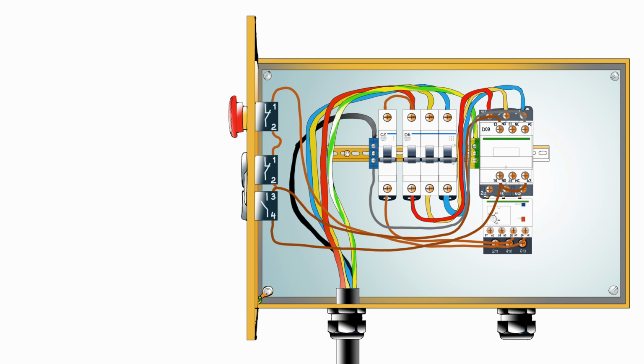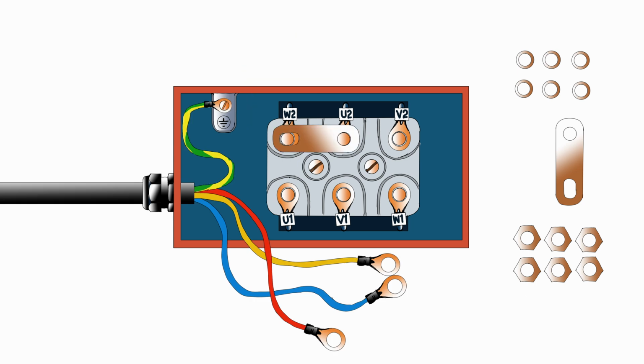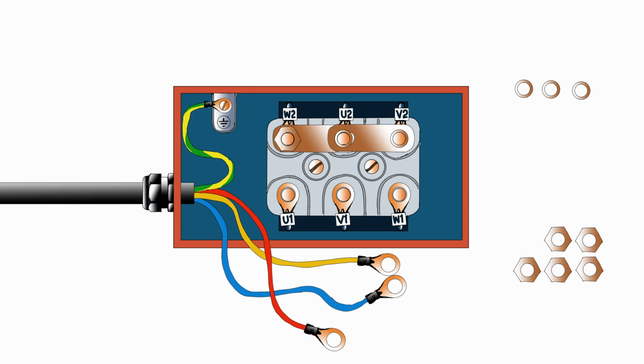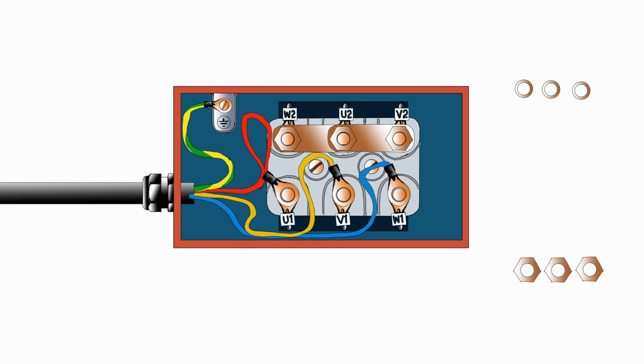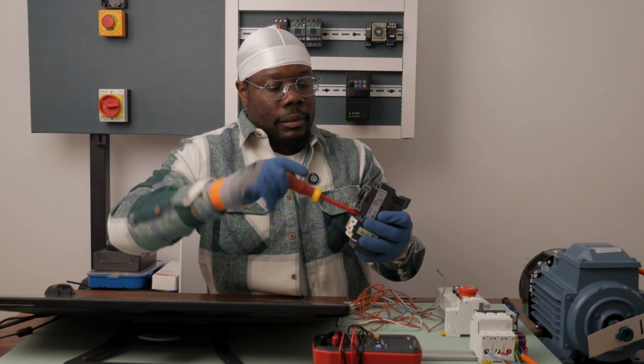The bottom of our contactor is linked with our overload relay, and we don't need to link it with any cables there. So we should always select an overload relay that is compatible with the type of contactor that we are using, to make sure that we don't create loose connections. And then from the bottom of our overload relay, we connect our supply cable that goes straight to our electric motor. For our electric motor on this exercise, remember, we connect it according to the manufacturer specifications, depending on the supply voltage that you have. Tighten.